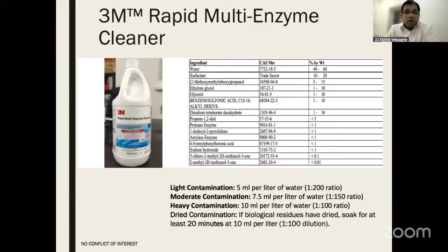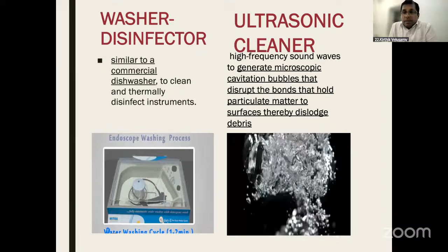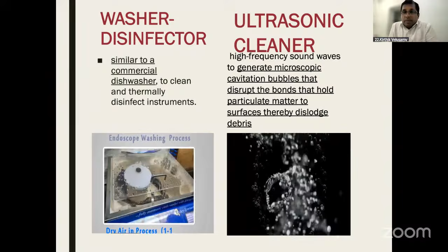There are a few centers having wash disinfector and ultrasonic cleaner. Little bit brief about that one. Wash disinfector, it's actually like a commercial dishwasher where it cleans the instrument and disinfects everything. In ultrasonic cleaner, it produces high frequency sound waves. This produces a cavitation bubble that disrupts the bond that holds the matter to the surfaces, thereby dislodging the debris. Ultrasonic cleaner is only a cleaner, it's not any disinfector.